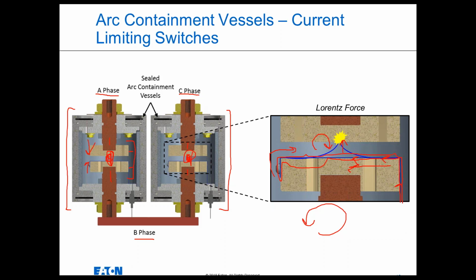Now, it may seem like we're walking a tightrope here. We want to create a path of lower impedance, but we want to add some impedance. So what if we add too much impedance and then it doesn't actually work? Well, that's a good question, and it does seem like a tightrope, but it's actually not, thanks to the UL 1558 standard, which governs metal enclosed switchgear.